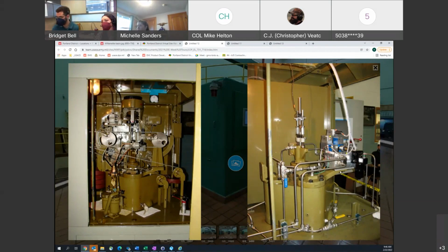Basically what we have here is a hydraulic oil manifold with multiple ports and passageways through it that the electrically controlled, PLC-controlled system will tell to go essentially left or right. That's a very small hydraulic spool moving back and forth, and that allows a small quantity of oil to go down into the larger chamber, the big yellow area. These are big, large hydraulic spools that fill that chamber, usually on average about 6 or 8 inches in diameter on the edges of the spool. The PLC controls all of this.